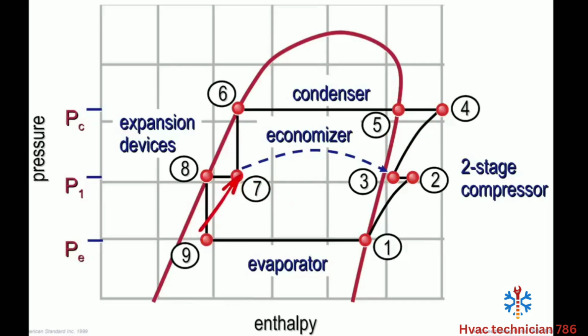So part of what that suction line, or that economizer line, coming back to the compressor does is pull that flash gas off of that liquid refrigerant, which lowers its total enthalpy and allows that liquid refrigerant to return to a fully liquid state before getting sent to the final flash plate at point 9.